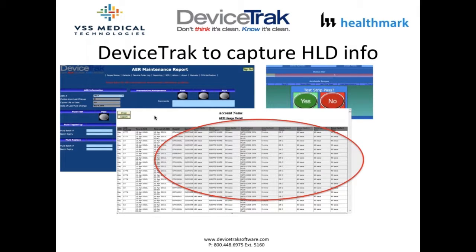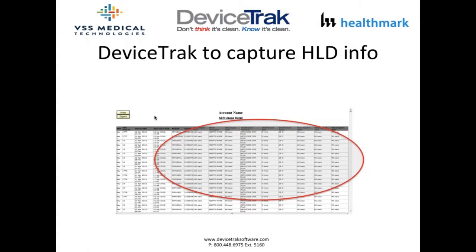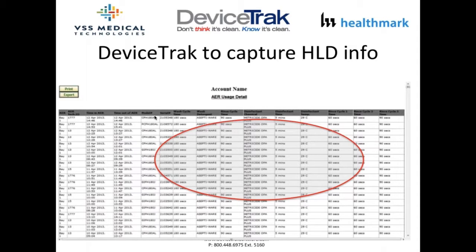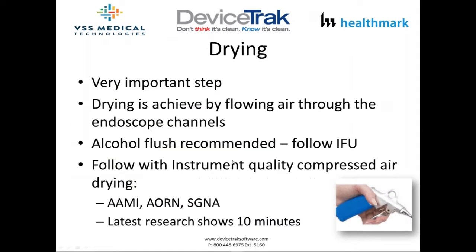DeviceTrak tracks HLD expiration dates, lot numbers, replacement dates, and serial numbers for your AERs. It captures confirmation of disinfectant minimum effective concentration via test strips and tracks all exposure times and temperatures for your particular AER. The system also automates your current manual logs, helping you become a paperless environment.